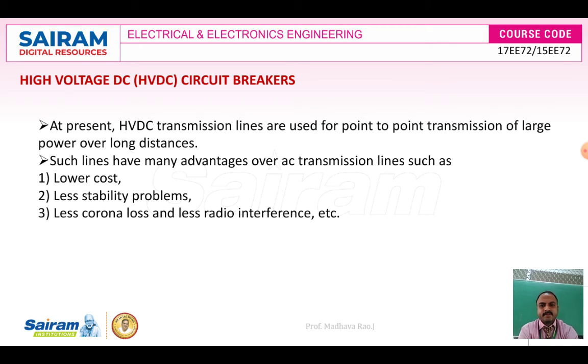HVDC transmission has many advantages: low cost, fewer stability problems, less corona. Corona means you see a nice blue voltage light around the conductor. That type of problem will not be there in HVDC transmission. And there is less radio interference, since the magnitude of the current and the magnitude of the voltage are always constant with respect to time. So no corona, no radio interference, right?